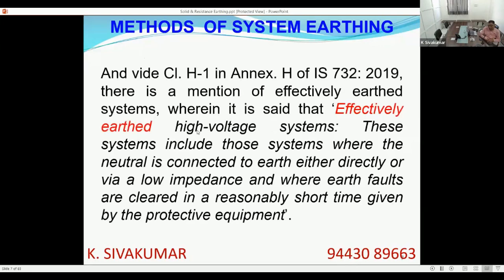Then if you see IS 732, the next important standard, here also in one particular class, it mentions effectively earthed system as a passing comment, effectively earthed high voltage system. Here it says neutral is connected directly or through a very, very low impedance where earth faults are cleared in a very quick time. So to be qualified as an effectively earthed system, the earth fault impedance should be very, very negligible. That is what is said here.